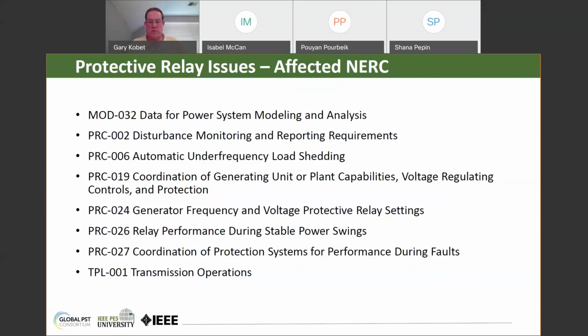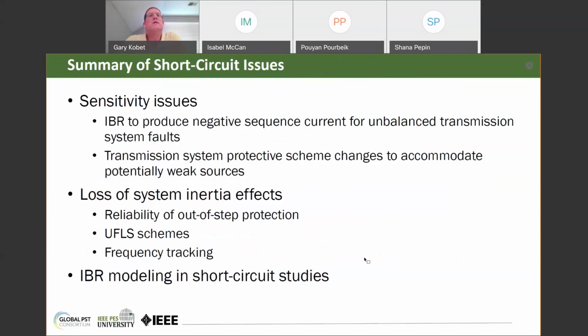And then in summary, on my last slide here, the summary of short circuit issues. One of the big issues is sensitivity issues, that there will be enough fault current with the right phase angle relationship for protection systems to discriminate between faults and load, and transmission system protective scheme changes that will be necessary to accommodate potentially weak sources when it comes to the fault current. And line current differential, directional comparison schemes with possibly direct transfer trip, that kind of thing.